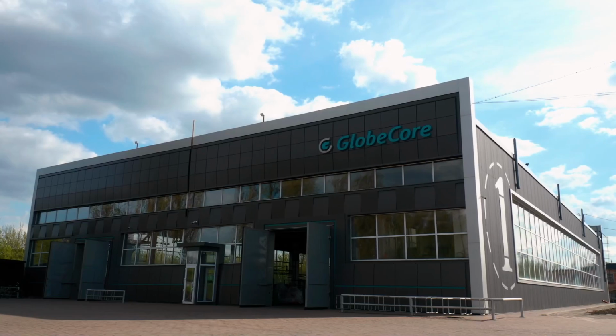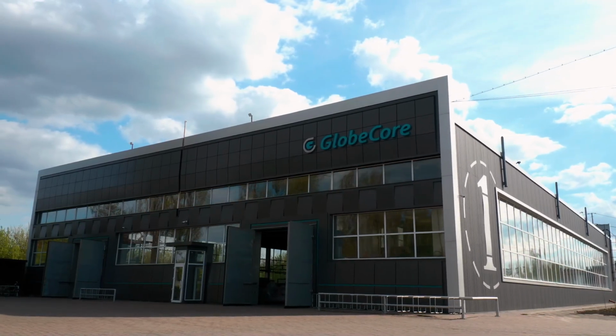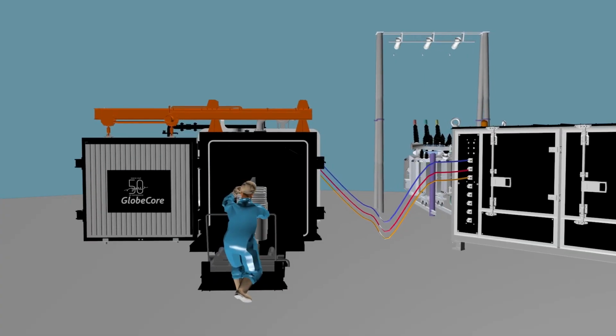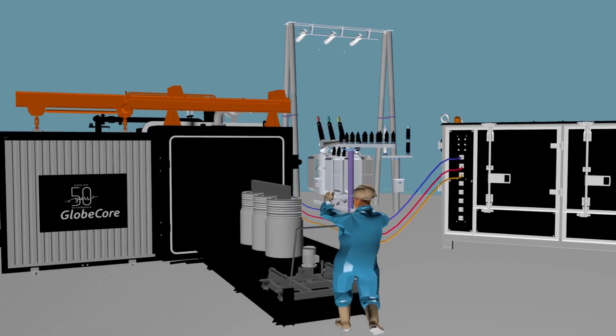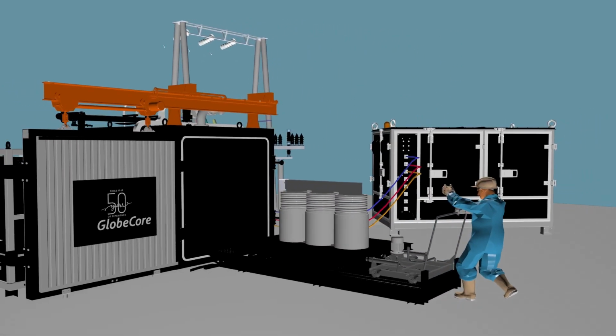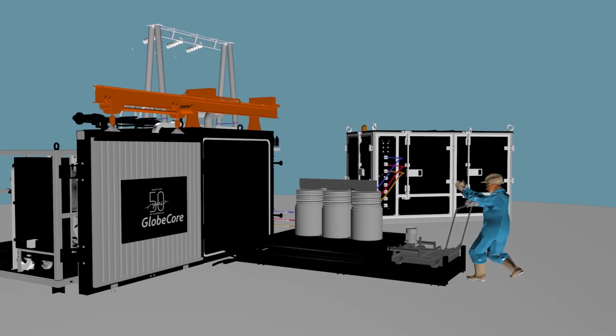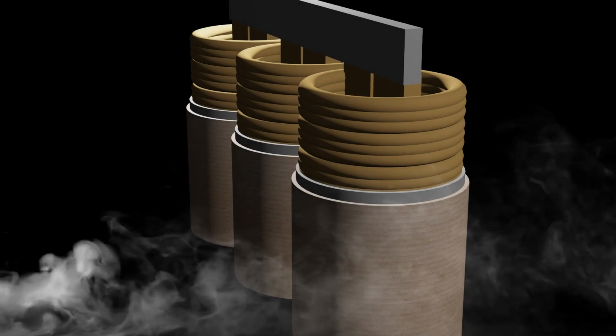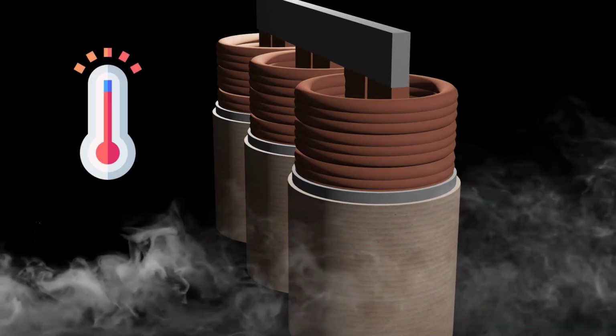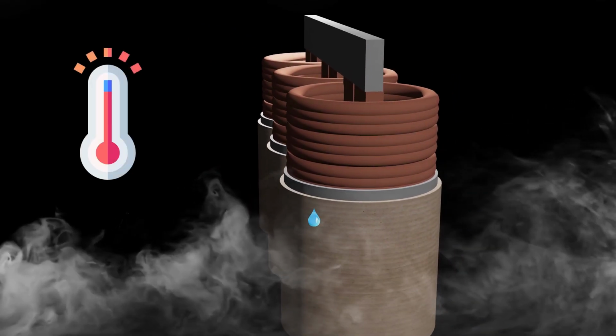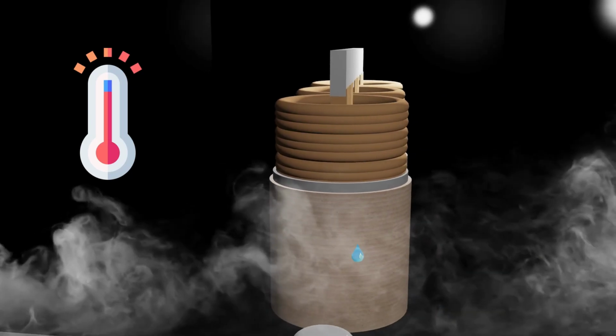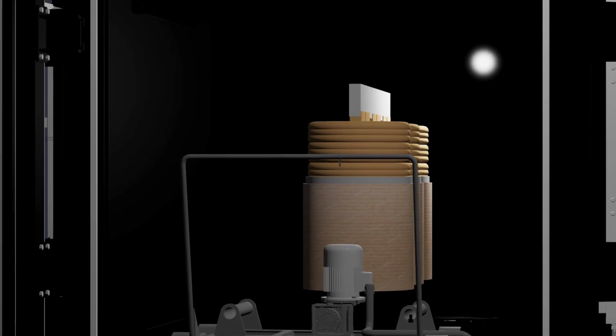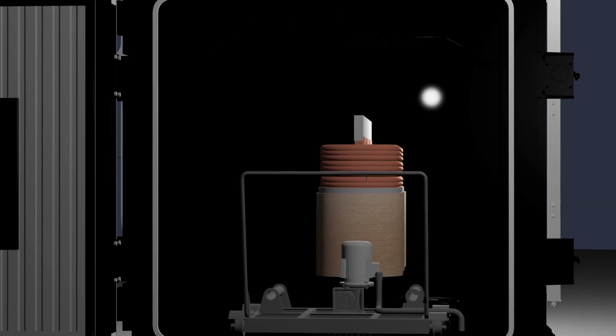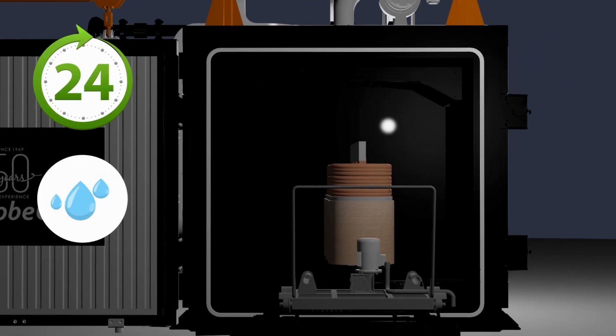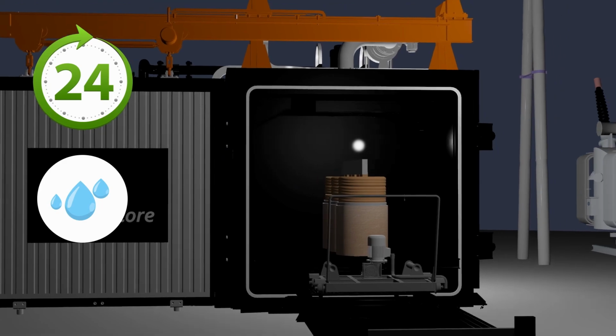1. Efficiency. The combination of a low-frequency heater and a vacuum oven ensures a smoother and deeper moisture removal process than in the event of each single method. 2. Safety. The approach reduces the risk of overheating the windings, because the vacuum allows the water to evaporate at lower temperatures. 3. Speed. The combined technique can reduce the drying time by up to 50% compared to using, for example, a vacuum oven only.